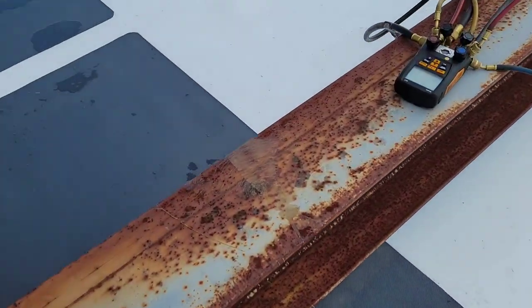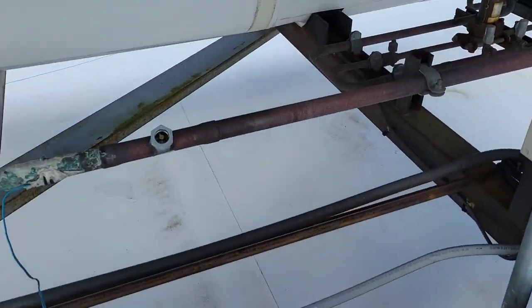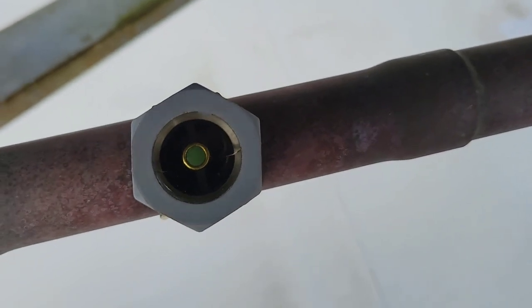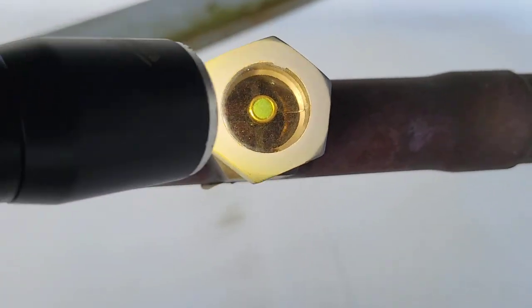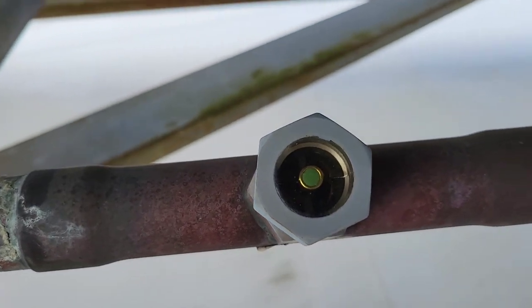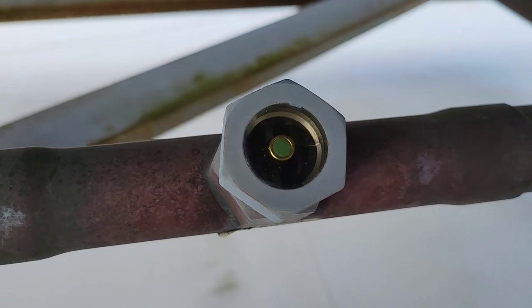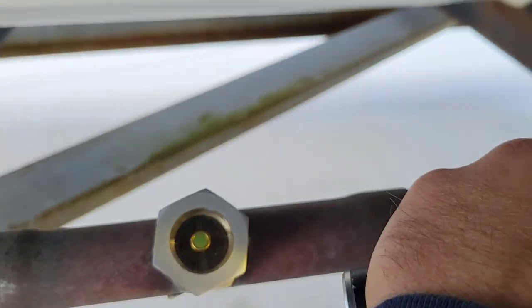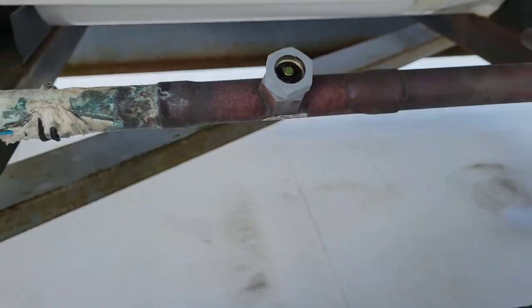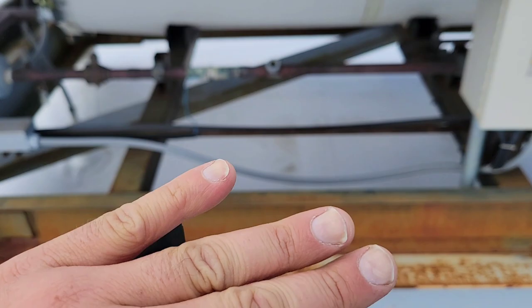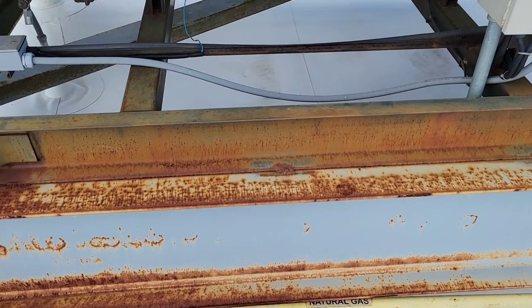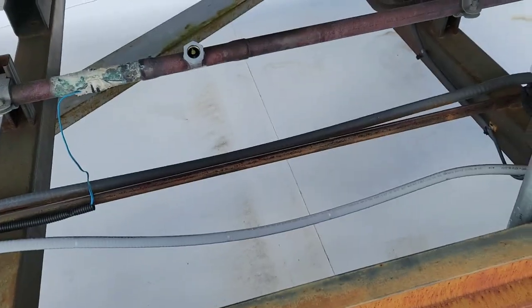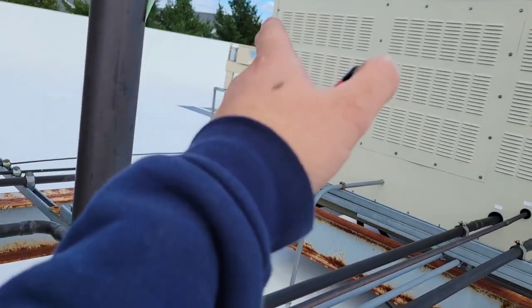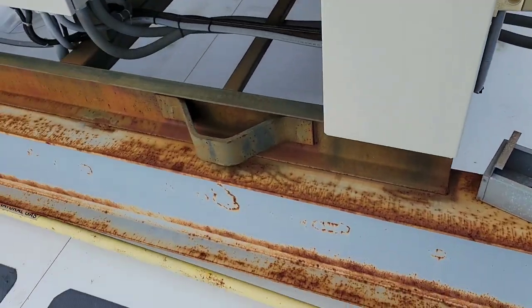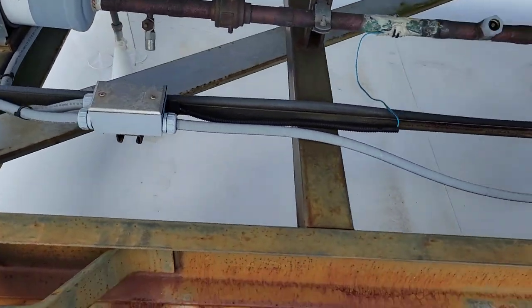So 10% is pretty good. And we're going to come over here, and I hate these sight glasses so much, but these ones are a little odd. You see how there's a line there, right? Sometimes you would think to yourself, oh, that's flashing. It could be a low load of refrigerant, but as far as I've been able to read these things, you want to imagine that you're looking in on the pipe and that pipe is a full column of refrigerant. It's almost like you're looking down on a river with these awkward cockeyed sight glasses. If you're confused, you can go check the other rack as well and see if it has something similar. But anyway, the refrigerant level looks good.